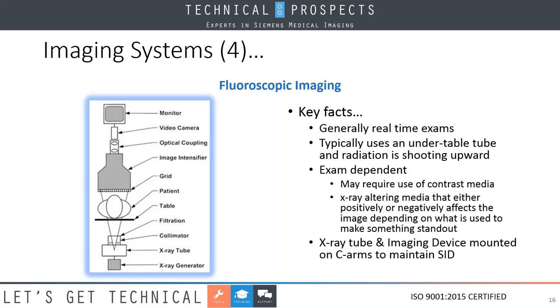One of the things that we do use in fluoro is contrast media. Depending on whether they inject either a solution or air, it will create either a positive or negative contrast on the patient to make something show up on the X-ray a little bit more clearly. And even on your hardwired systems that have both rad and fluoro, the combination of the spot film tower down to the X-ray tube is also considered a C. It's more square, but is still considered a C, as opposed to the nice smooth rotations of our portable fluoro systems today.